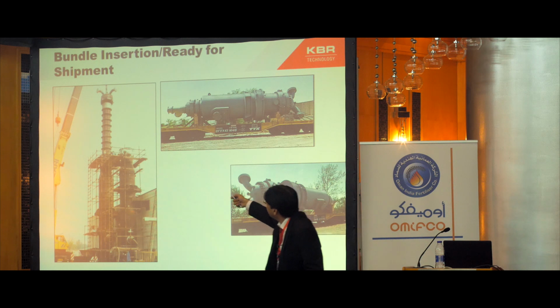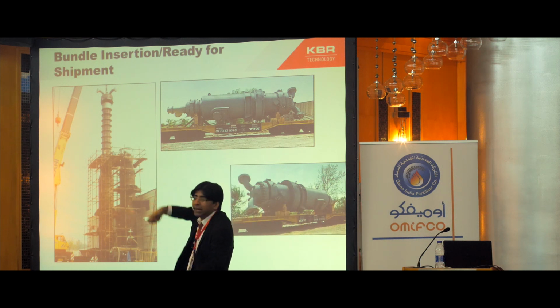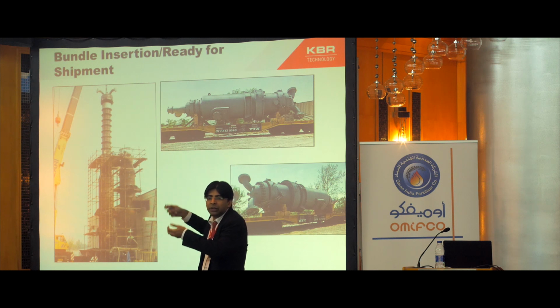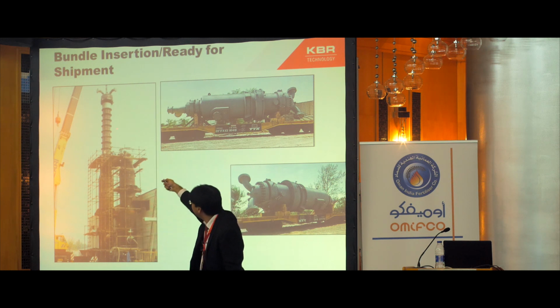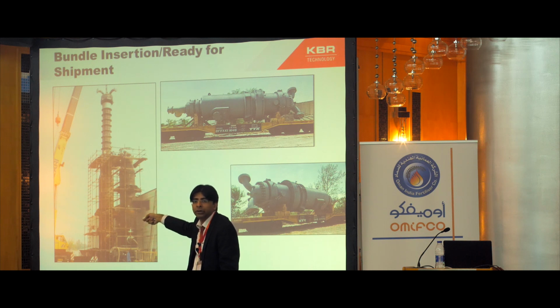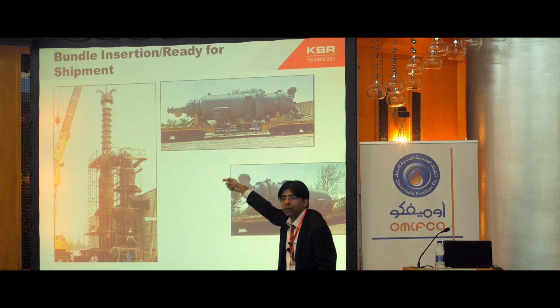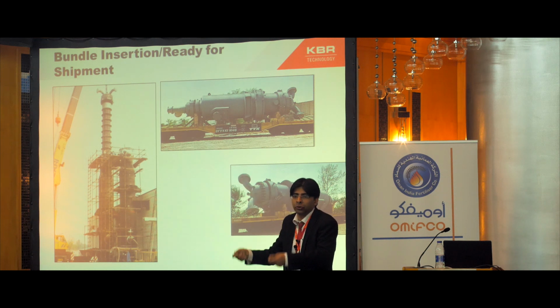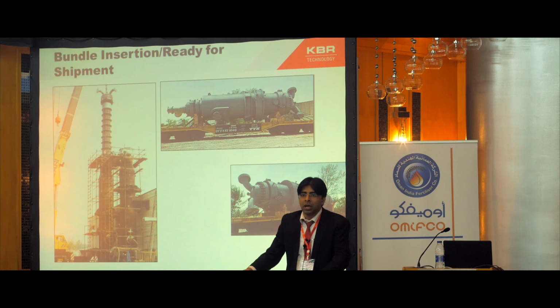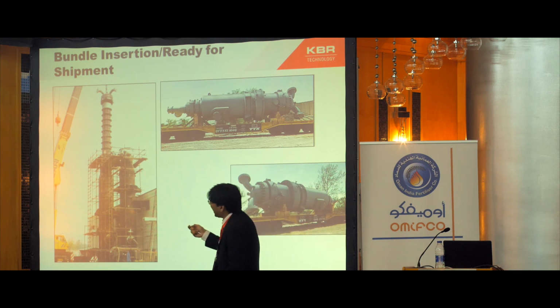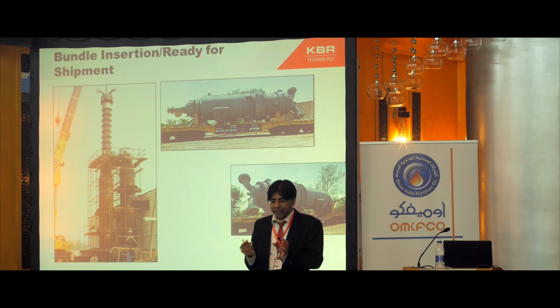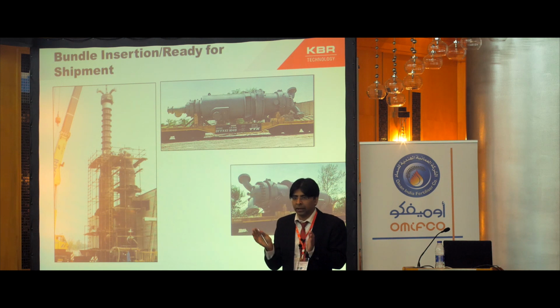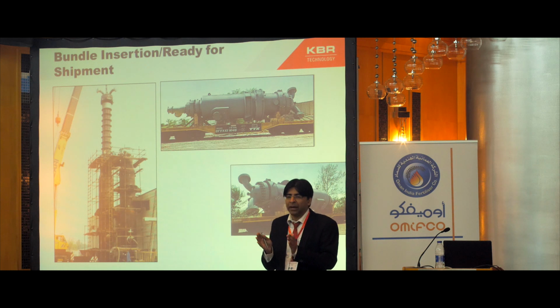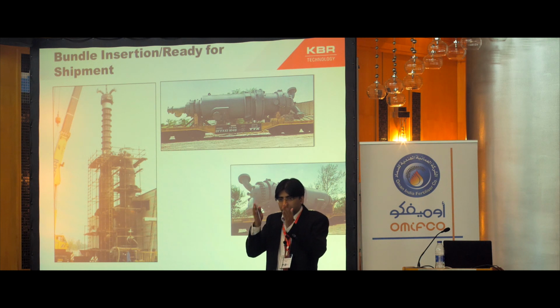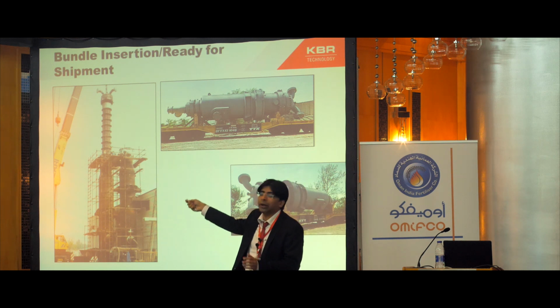The design is such that this channel completely comes out with the bundle, so it can be easily fitted inside the boiler, inside this exchanger. So there is no issue in connecting the tube, basically putting the bundle down. Also, the design is such that at normal operating conditions the refractory and the bundle are very close together, but at ambient temperature it separates out. So it's very smooth and it can be done very easily using the crane.